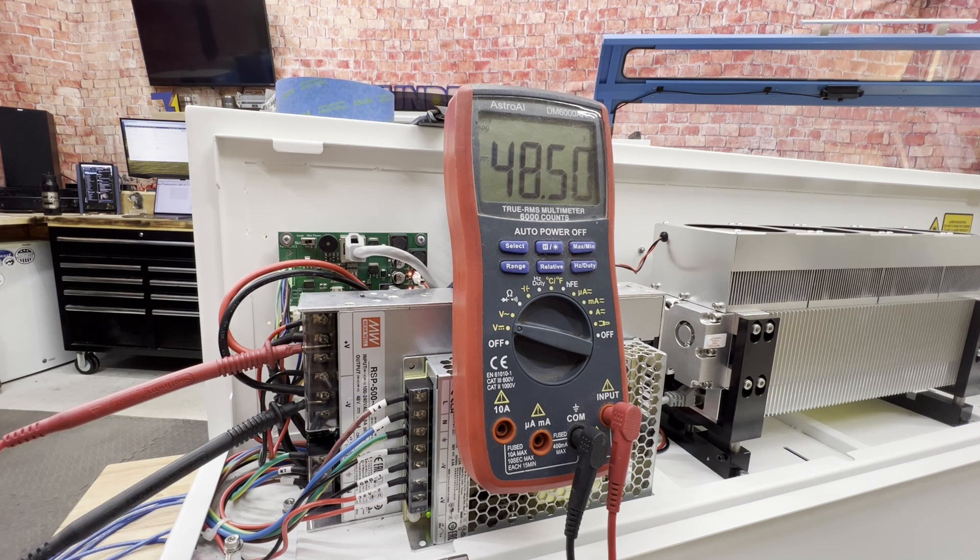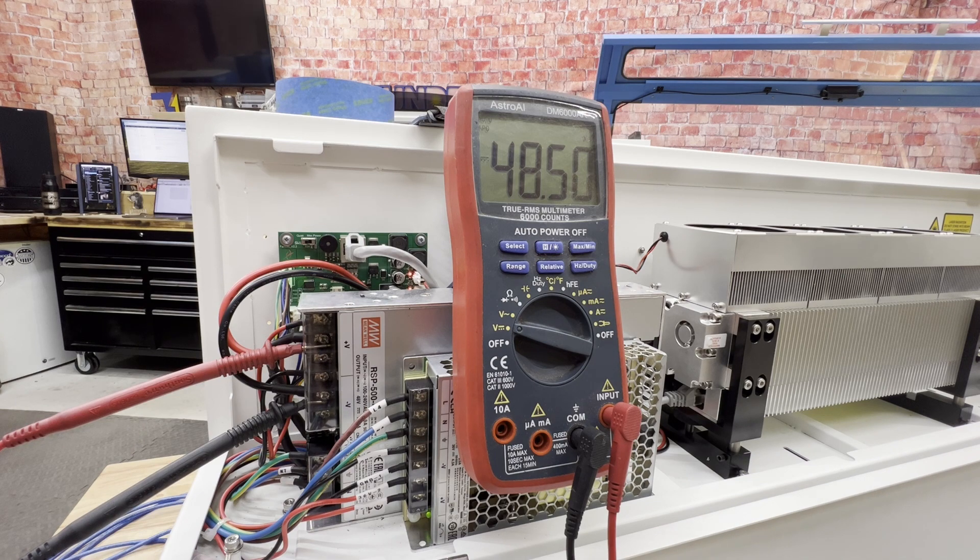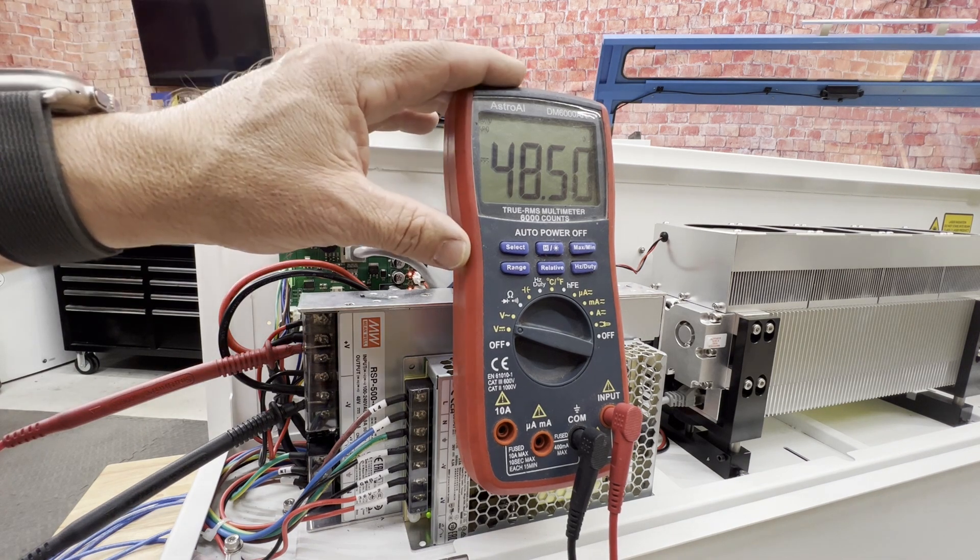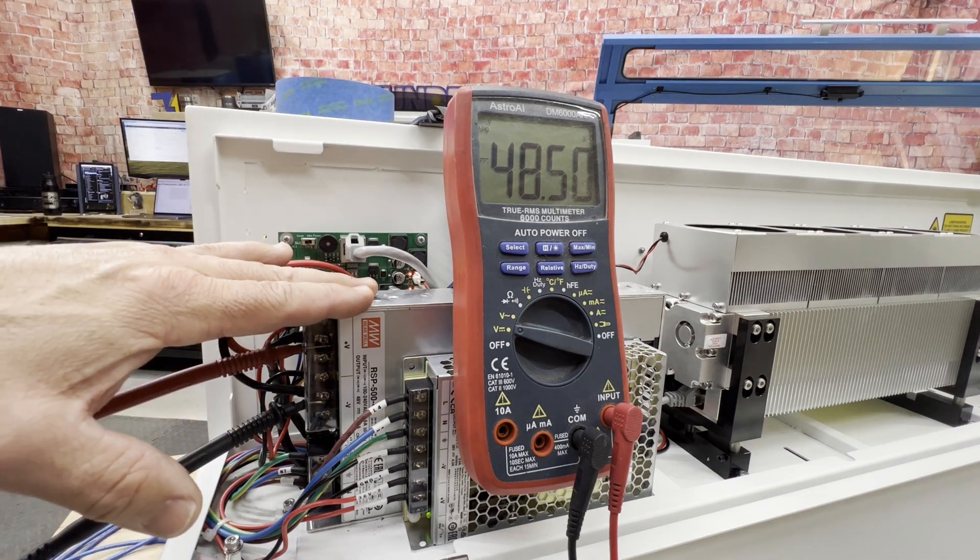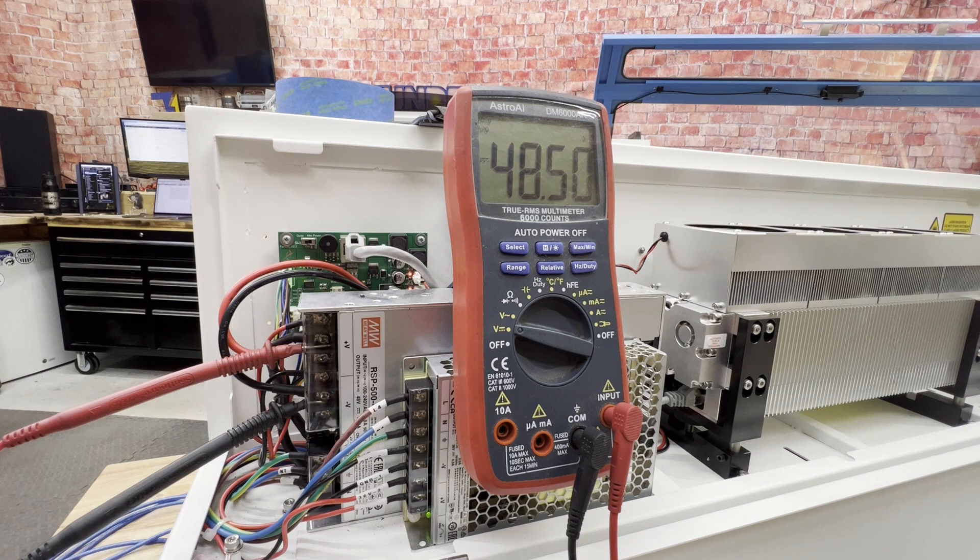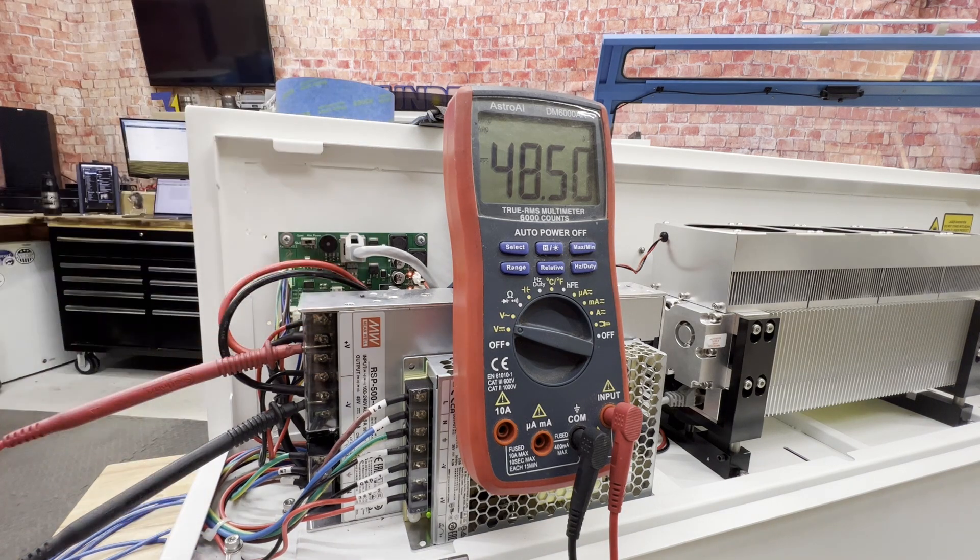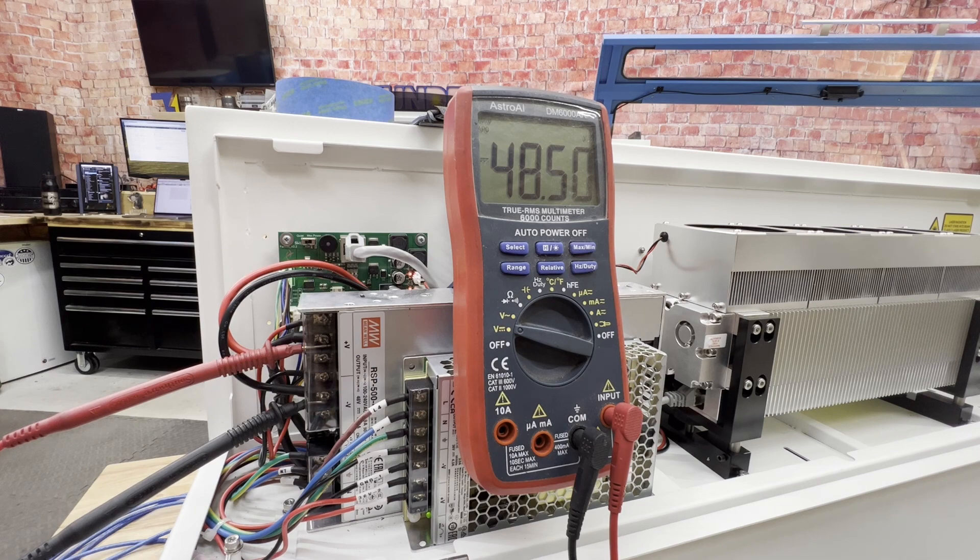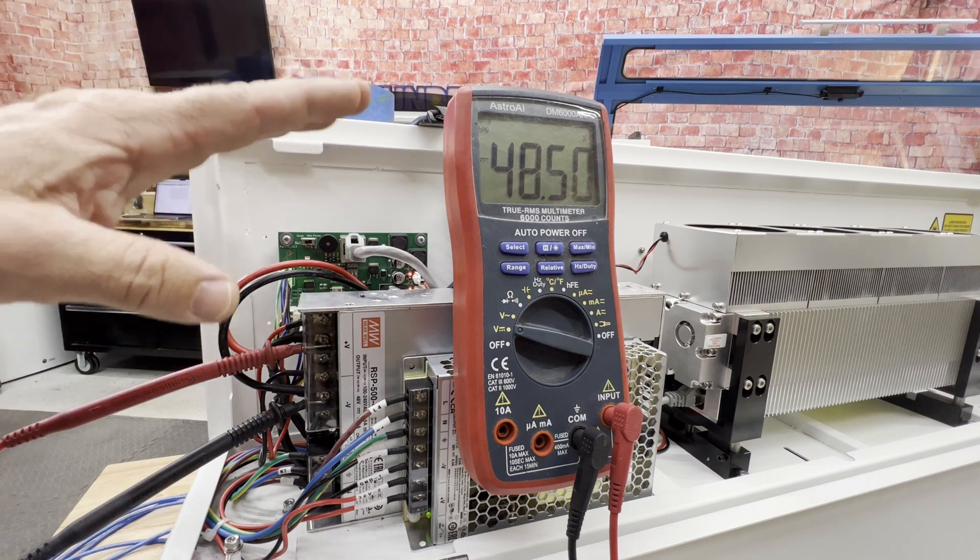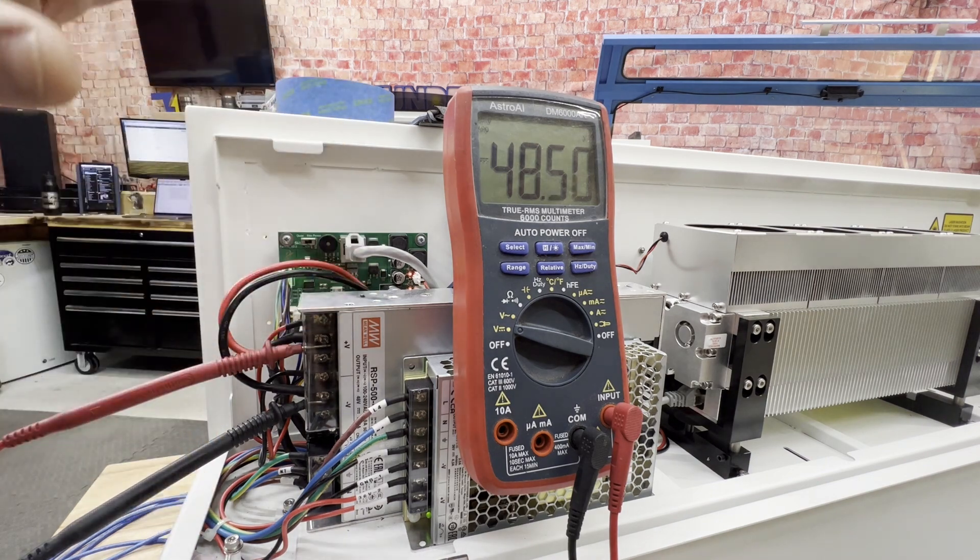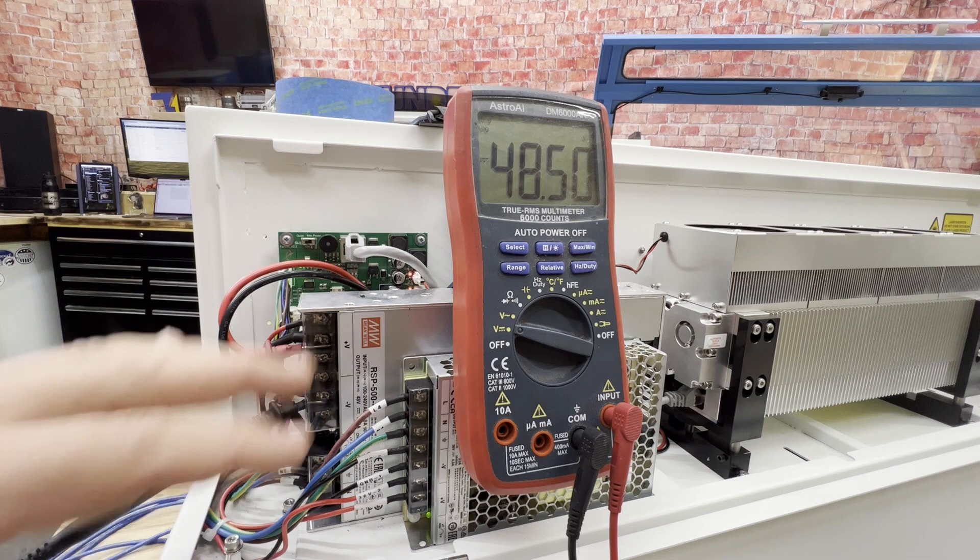So once we have this metered and it checks out, maybe we're a little out of tolerance, we can adjust and compensate for any errors. We'll reboot the machine and test again. If we are not getting 48 volts then we have an issue with our 48 volt power supply. At that point you would just continue to work with us in the ticket system so that we can get you a new one or do a little bit more research going forward.